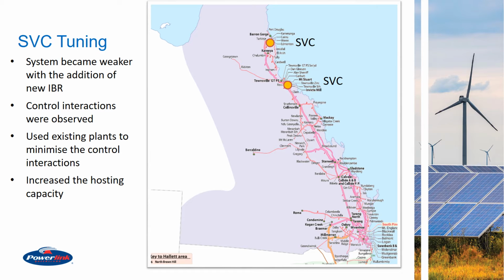What we saw in North Queensland, as more and more IBRs were connected, the system became weaker, and we started to observe some control interactions. These two SVCs, because of their control structure, provided some flexibility to modify their control system, and we worked closely with the manufacturer of those SVCs and designed a different control system that basically reduced the control interactions and increased the hosting capacity of that region by a few hundred megawatt without actually adding any fault level or, in other words, synchronous support.